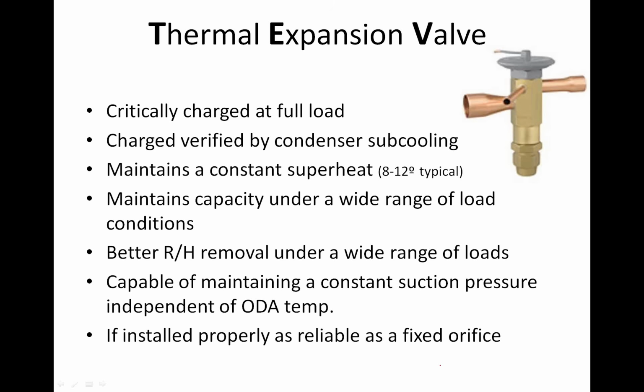And basically what will happen is, if we have a very long line set, the pressure drop will cause the refrigerant to flash into a gas, and we'll lose our subcooling. So we may have 10 degrees at the condenser outlet, but because of a huge long line set and maybe a lot of lift, there's so much pressure drop that we have maybe 0 degrees of subcooling by the time we hit the expansion valve.